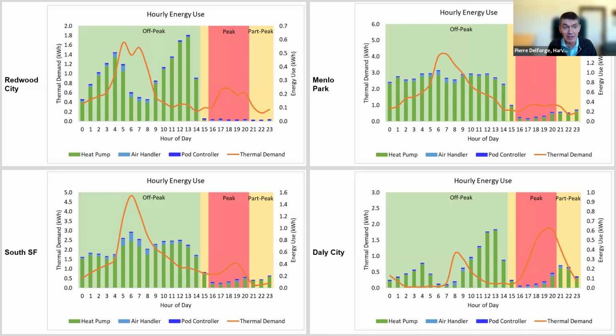And you can see in green, the green bars are the heat pump operation, which is largely off-peak. Green, yellow, red are the peak prices on time of use rates for PG&E. So in some cases nearly 100%, in some cases 90% of the load was off-peak. Depending on the home, some of them had almost no usage on peak at all for the 9 hours from 3 p.m. to midnight. Some of them had a little bit of usage. Those were early versions of the system that didn't have the backup heat pump. They only had the Sanco2. So the Sanco2, on some cold winter days, had to kick in at night, in the evening, a little bit to meet the load.